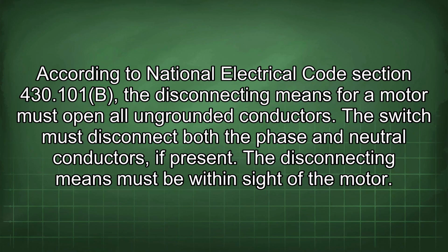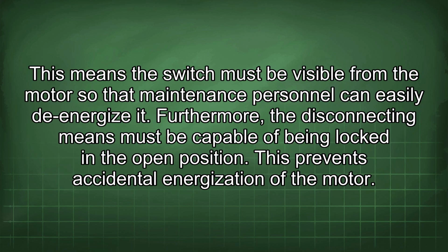According to National Electrical Code Section 430.101(b), the disconnecting means for a motor must open all ungrounded conductors. The switch must disconnect both the phase and neutral conductors, if present. The disconnecting means must be within sight of the motor. This means the switch must be visible from the motor so that maintenance personnel can easily de-energize it.